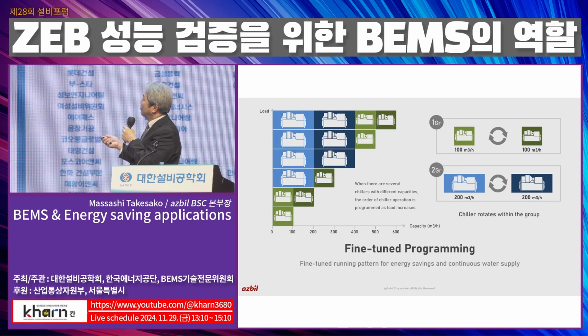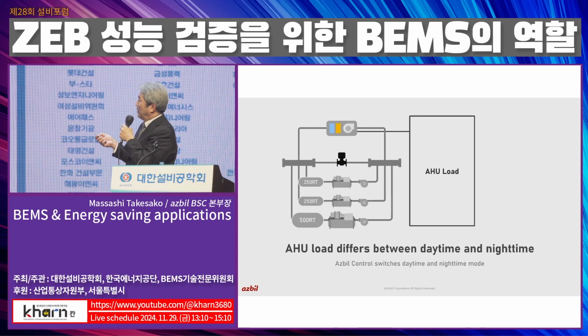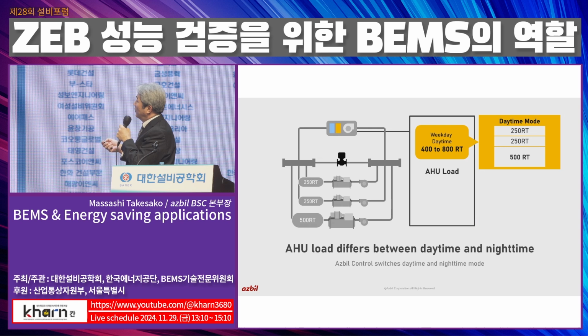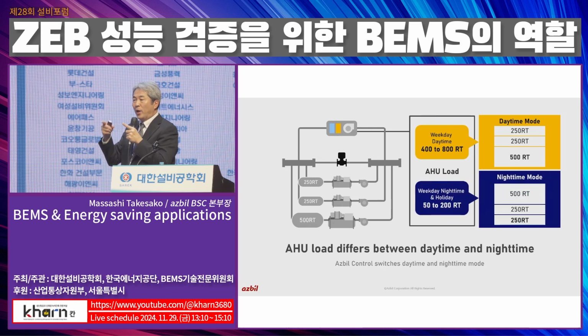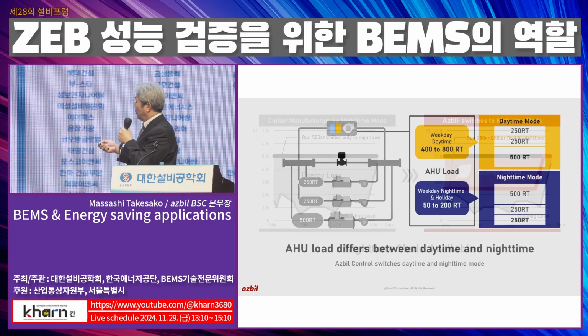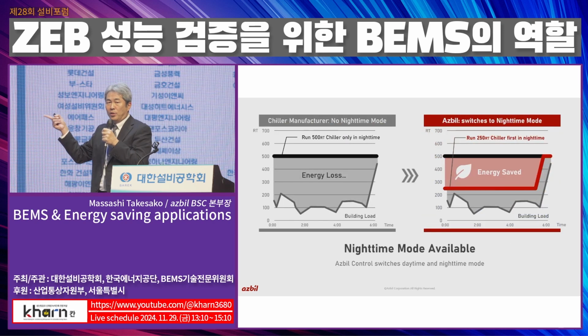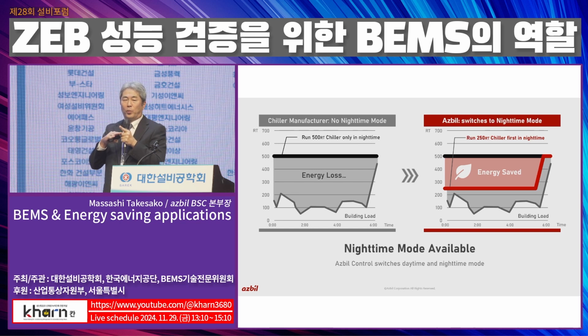The next one is also very simple. Daytime and nighttime load trends are totally different in characteristic. So on weekdays, during daytime and nighttime, the priority of the chillers can be changed accordingly. As a result, we can minimize energy loss from inappropriate chiller capacity. Most chillers have a characteristic where partial load results in very low efficiency, so to avoid this we have to choose the most appropriate capacity chillers. That is also one of the very simple controls.